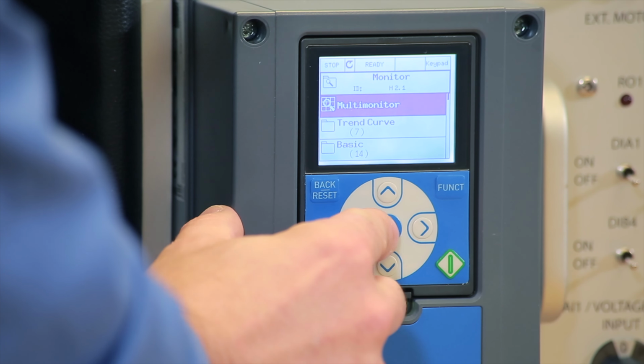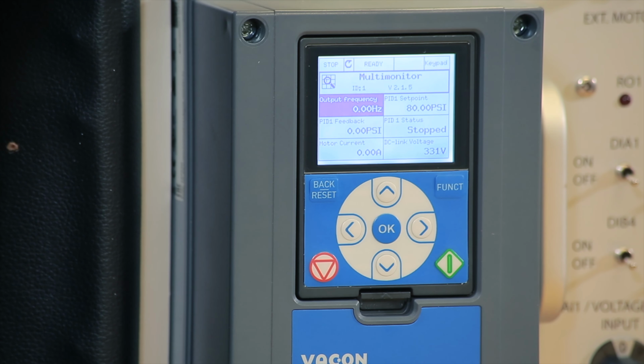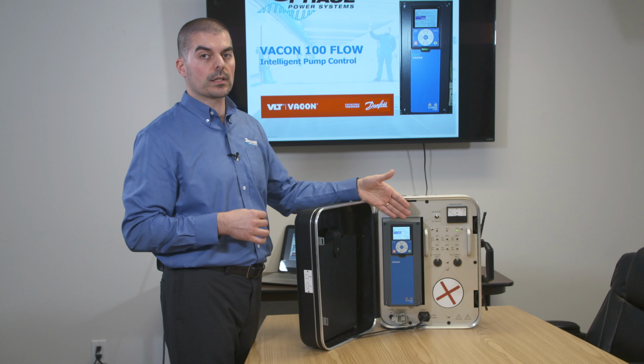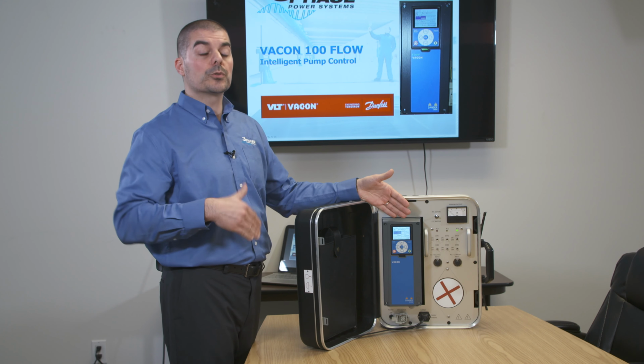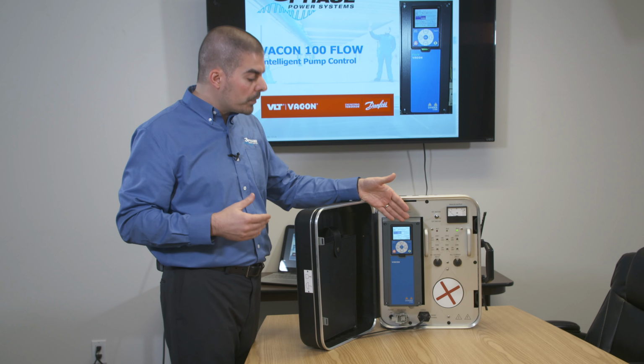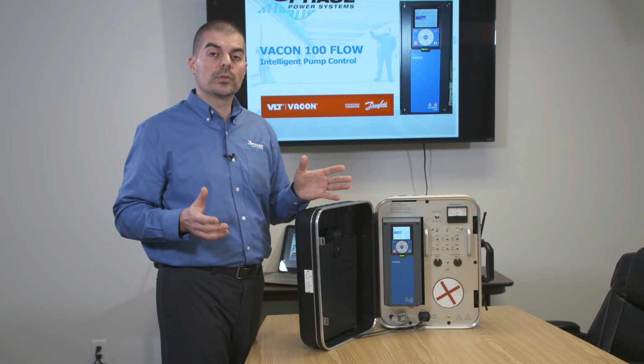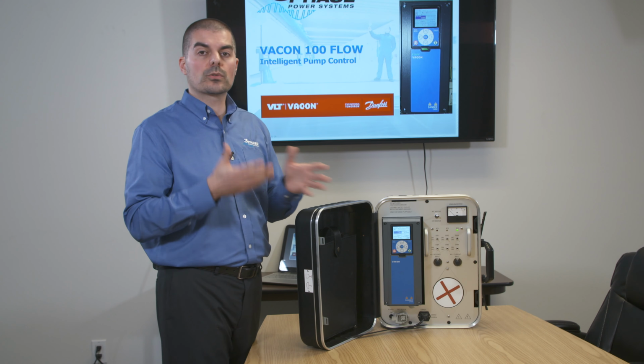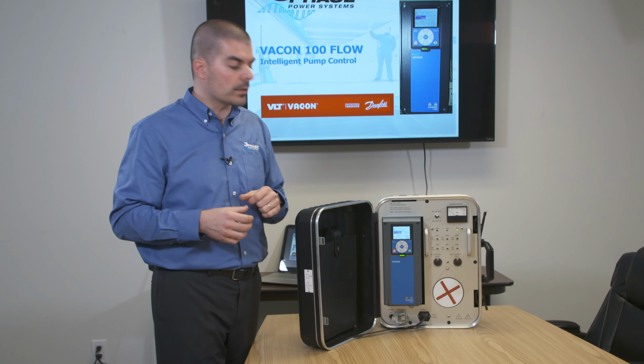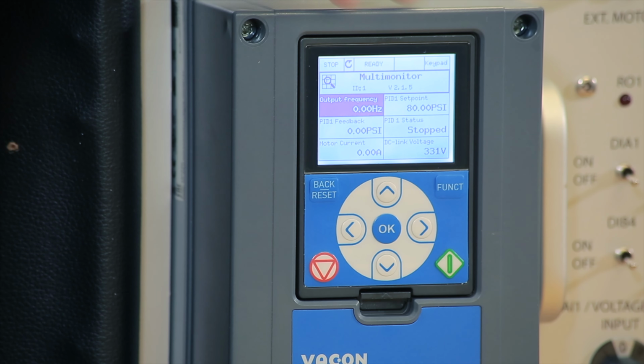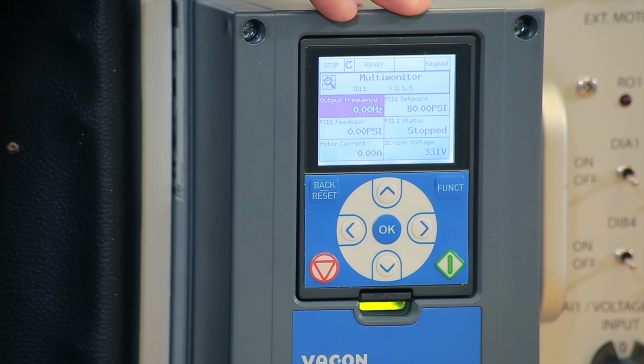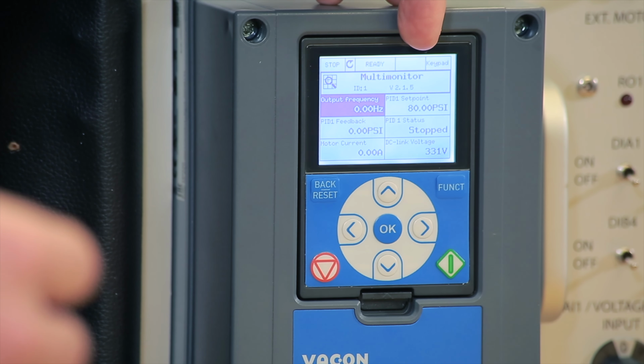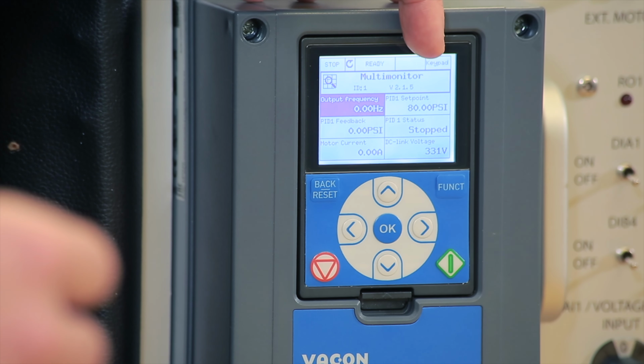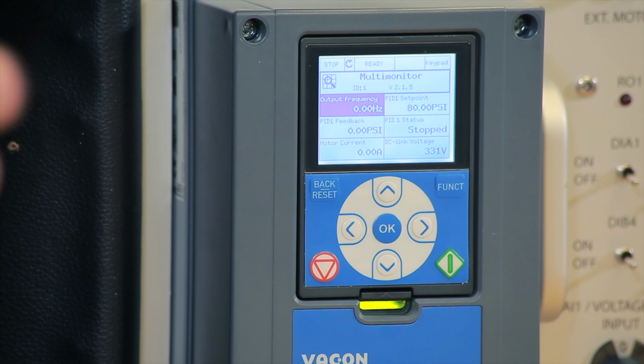Multi-monitor is key, because by default, the drive lets us monitor up to 6 things. As you saw in the introduction of 100 Flow, this drive can monitor up to 9 different things all at the same time, which makes it super simple to use and very intuitive, and you don't need to scroll through menus to view different things, which is beautiful. Right now, by default, the drive displays output frequency, PID set point, PID feedback, PID status, motor current, and DC link voltage. For starters, we can leave them alone.